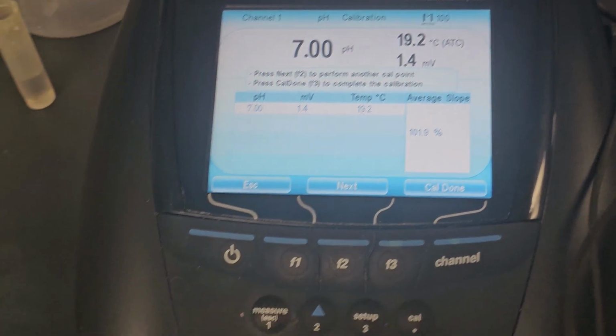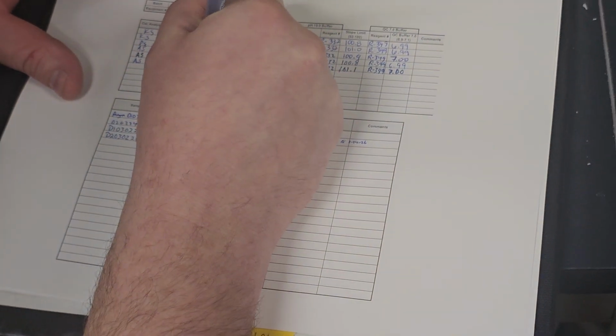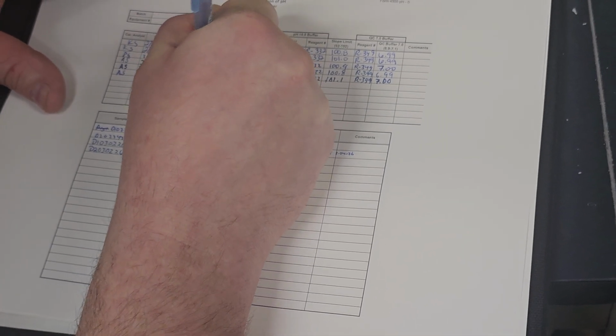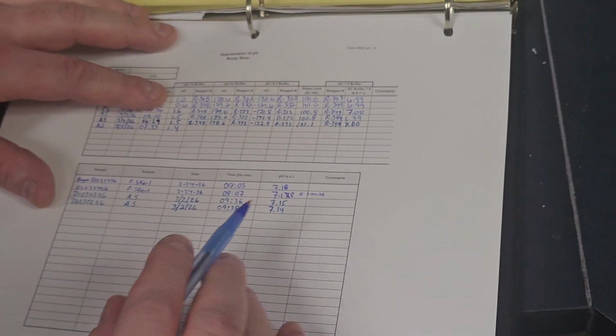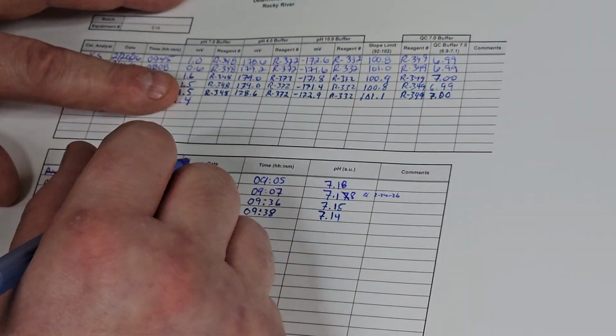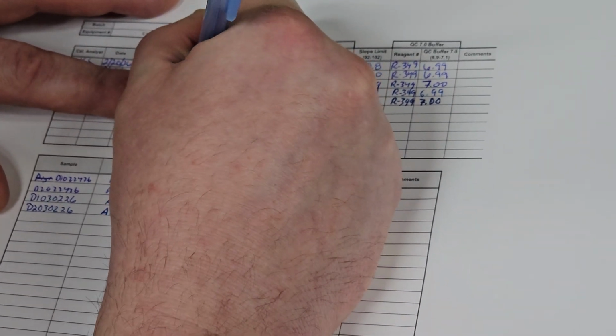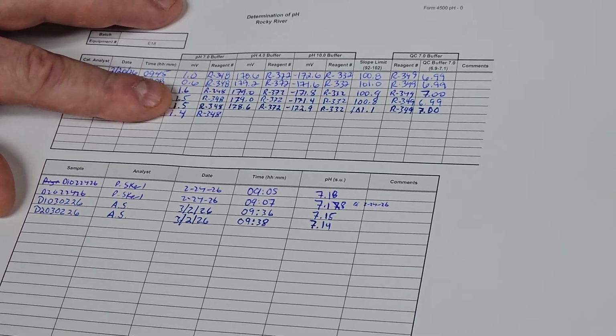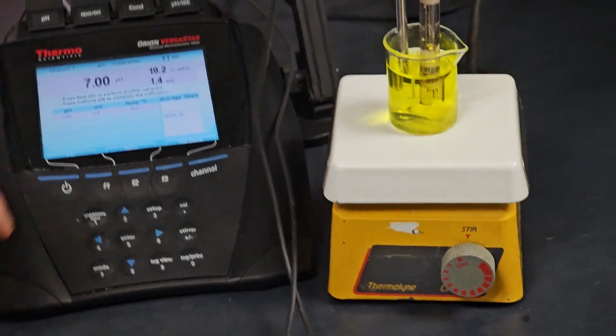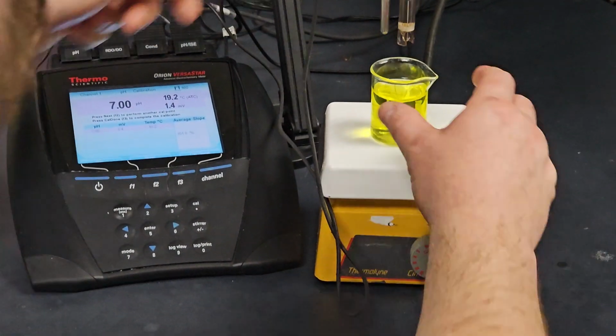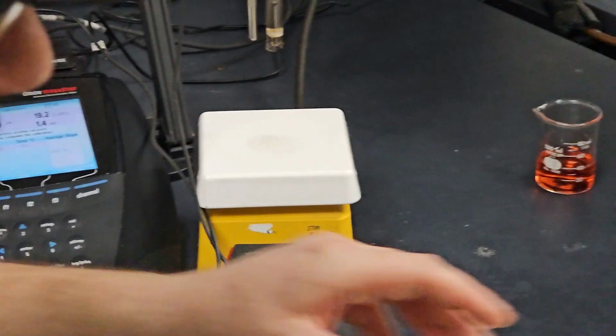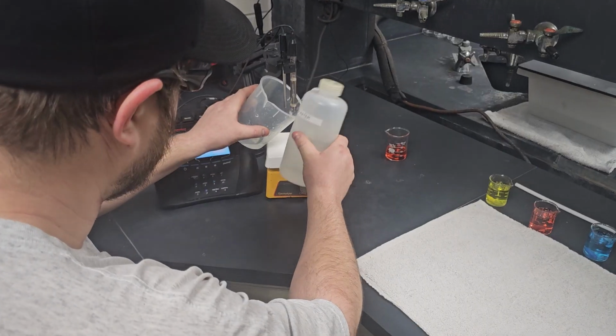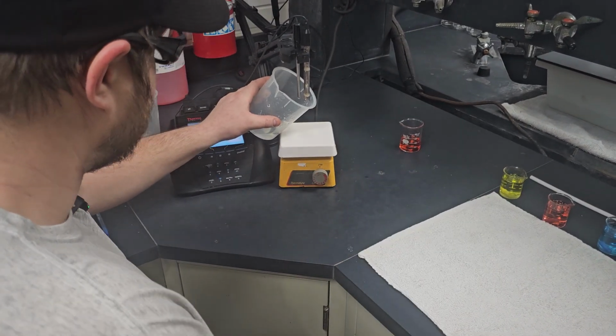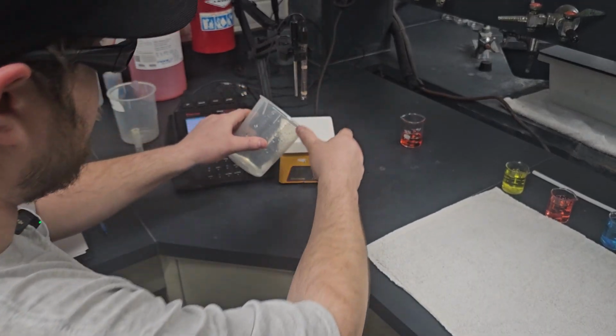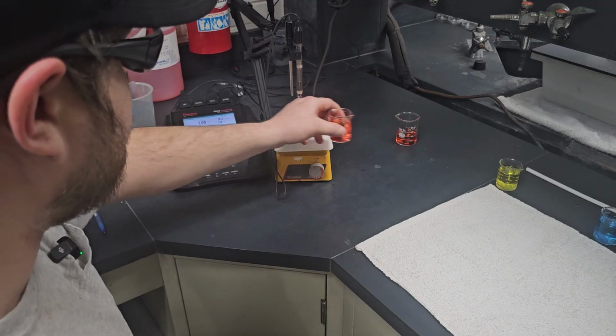on our calibration log sheet. So we have 1.4 millivolts, which you can see is comparable to other calibrations. And that reagent for the pH buffer 7 was the R348, which was written on the bottle next to the expiration date. So now we're going to move on to our next buffer solution. So you remove the probe from the 7. You rinse the probe with DI water. Gently shake the excess. A little bit's okay. And we're going to get our 4 buffer solution.